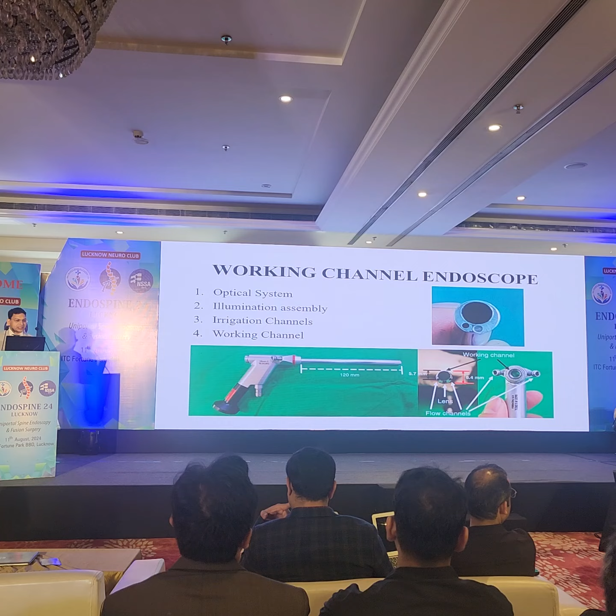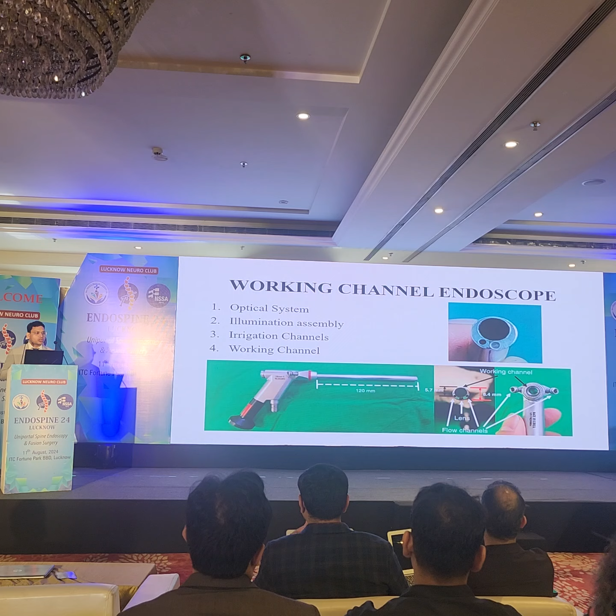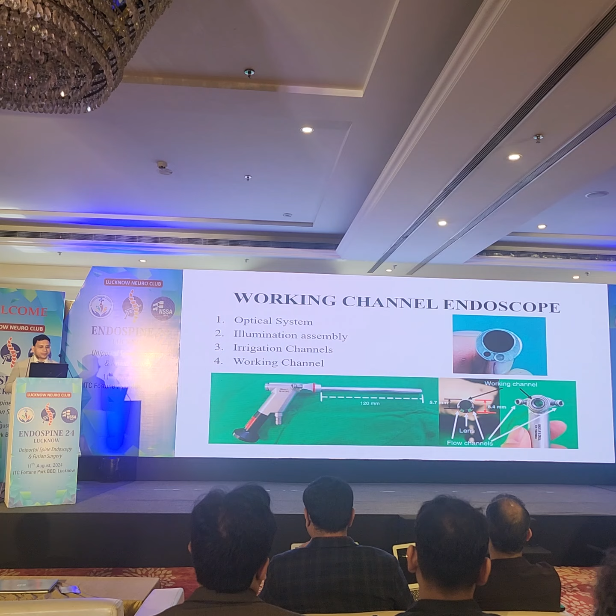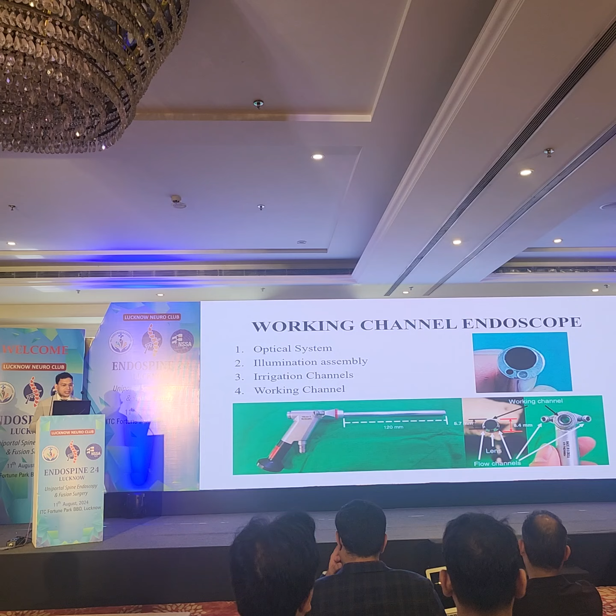So the first and the foremost and the most important instrument, and of course the most costly instrument, is the working channel endoscope. It is called a working channel endoscope because it has a lumen through which you have to pass your instruments, and you have to work through this corridor only. This working channel endoscope is divided into 4 parts: the optical system, the illumination assembly, the irrigation channels, and the working channel. You can see in the center we have the large hole, which is the working channel.